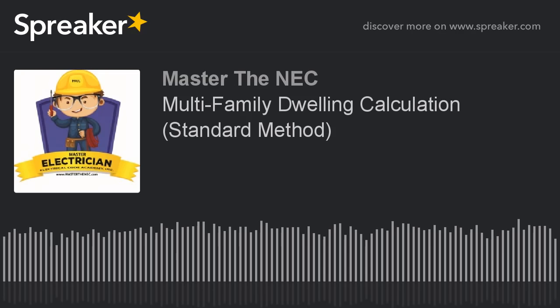Next thing, we're simply following down the items here, the applications, the articles in the code book. The next thing it says, we're going to deal with the electric clothes dryer. Well, we also said that the electric clothes dryer in this unit was 4.5 kW. It was a 120/240 volt load, so we obviously know there's going to be a value in both the neutral and the service column.